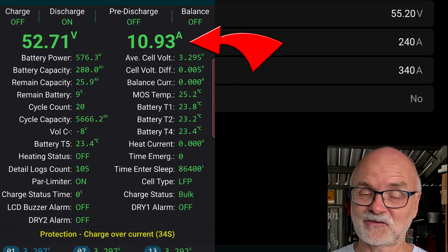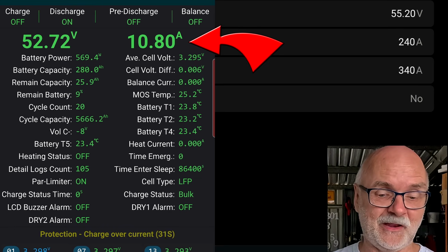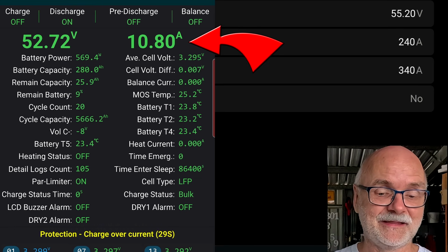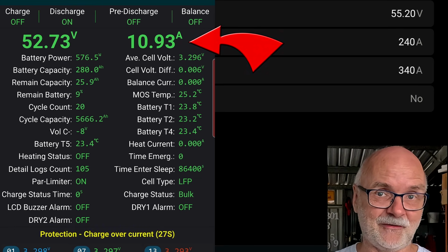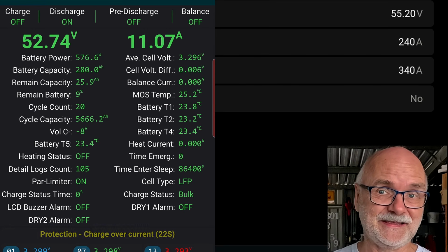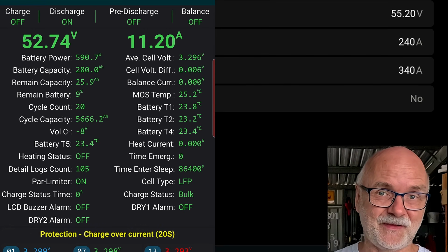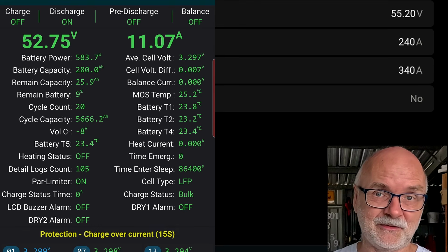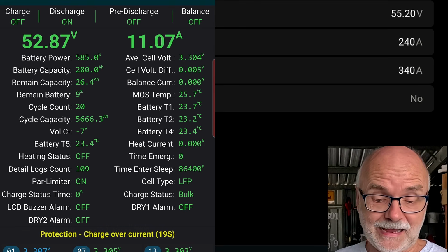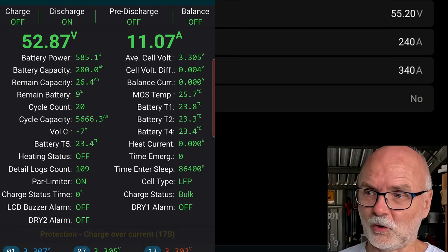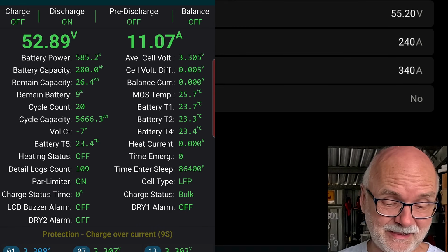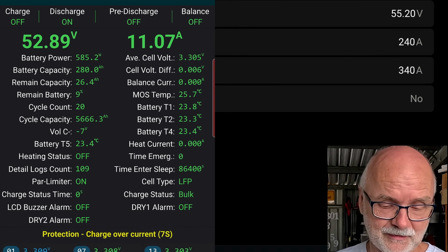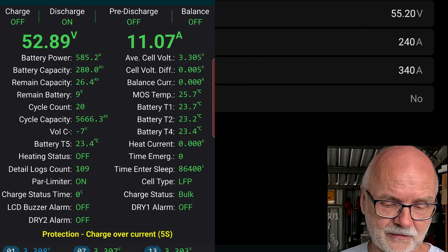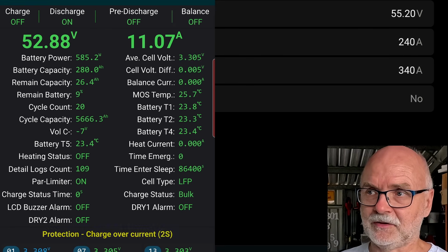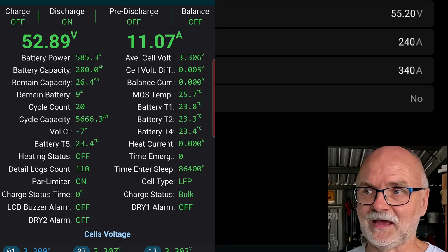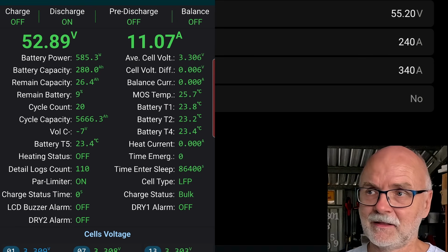Yeah, this is the difference to before. There was 0 amps going into the battery, but now we are allowing 10, 11 amps into the battery. So this parallel limiter is actually bypassing the MOSFETs and is charging the battery with a very small current. So now let's wait another 20 seconds until this fault clears here and see what happens with the current limiter active. So 7, 6, 5. What is going to happen? And what can we see with the CCL? Is it requesting more current again?